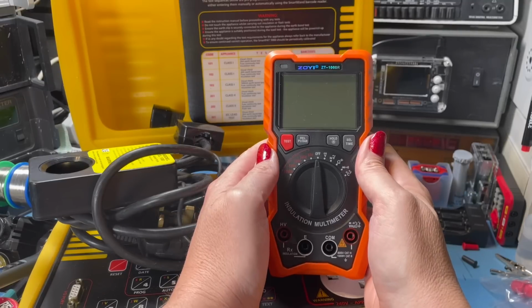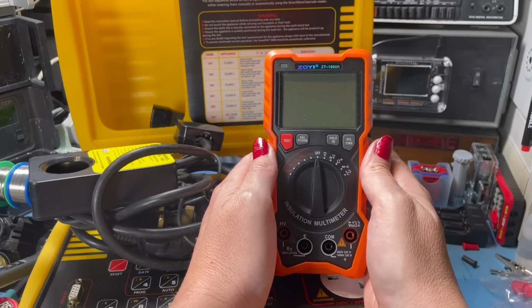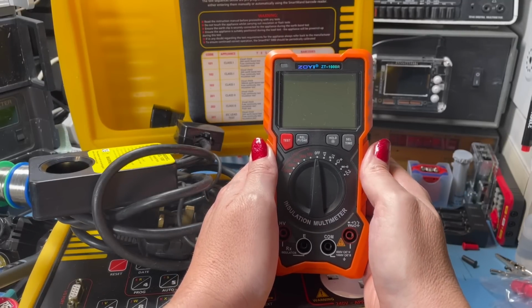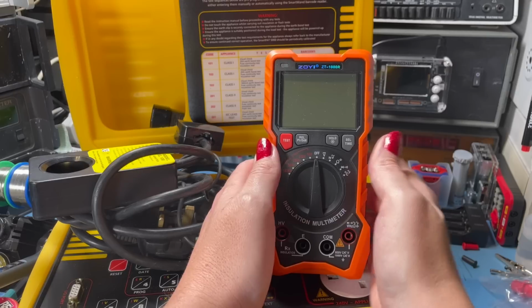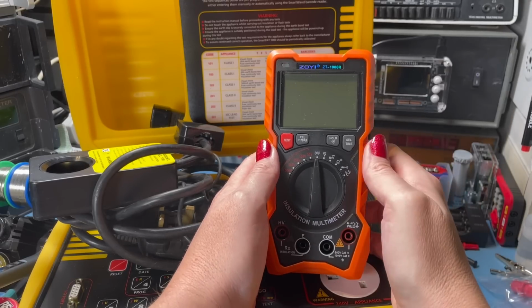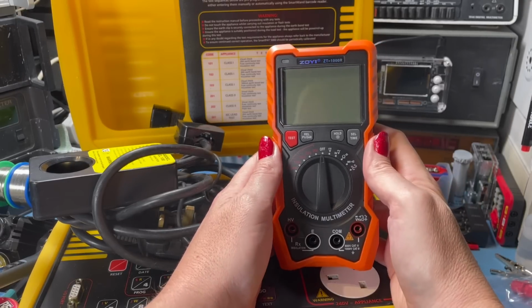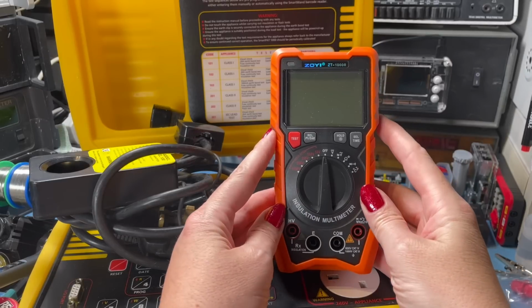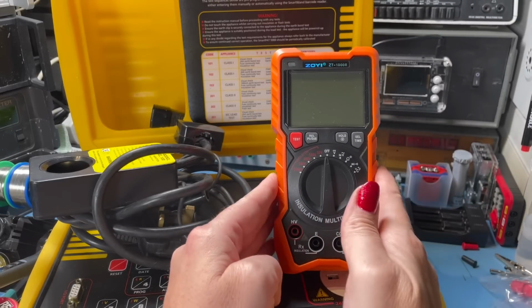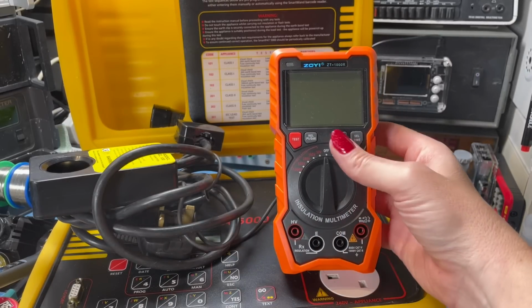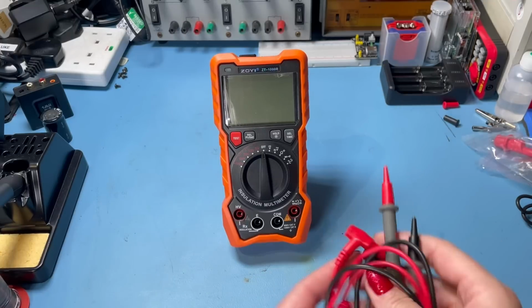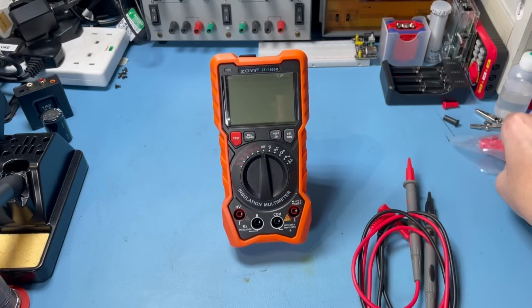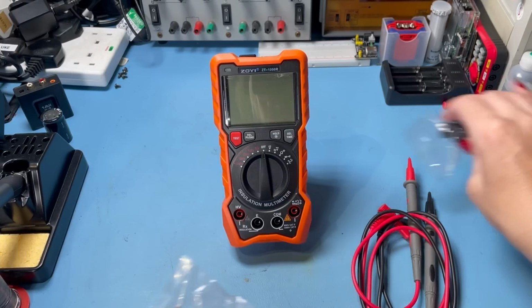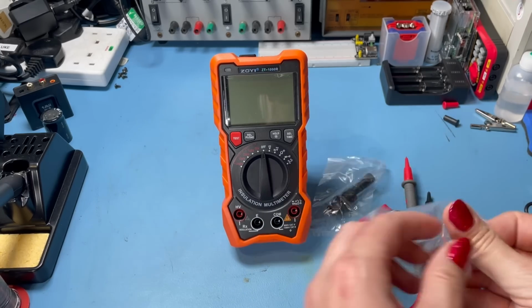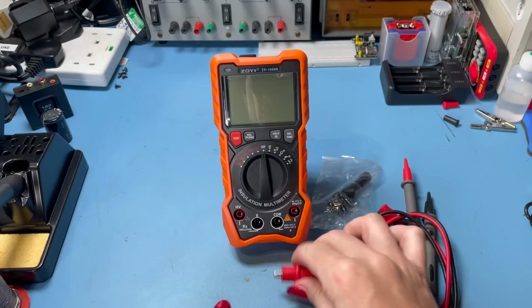Where this would come in really handy is testing the insulation in fixed wiring installations, to make sure the insulation hasn't failed on any of your cables, there's no breaks in your cables and stuff. But we can also use it to test extension leads, appliances, and even a transformer. Hey, I've got one right here. Right, so I've got my probes here, and I've got my insulation testing clips I can use.